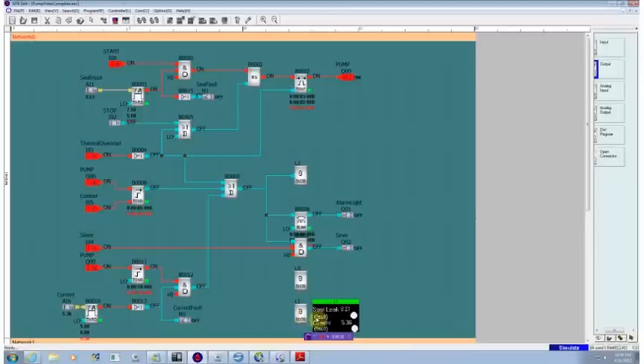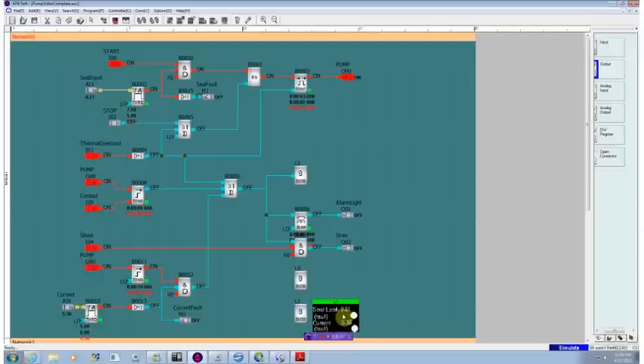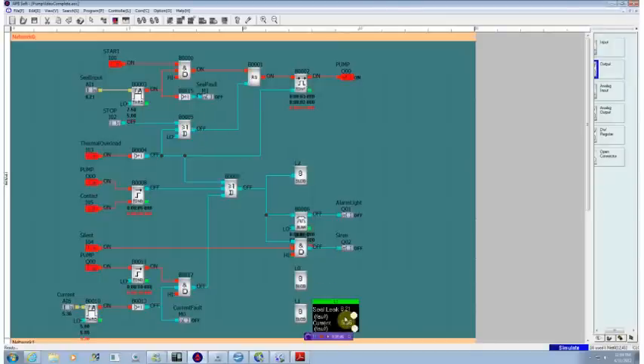If we take a look at our main maintenance screen, we see that the seal leak level is at 8.21. An astute operator would say that should be up close to ten. I probably have a leak condition developing. Not enough to impact the starting of the motor, but it's something that I should be looking at.